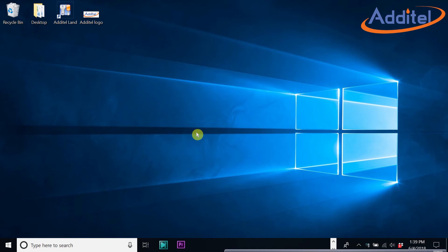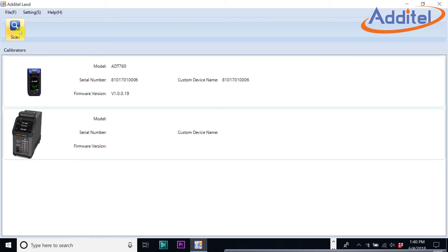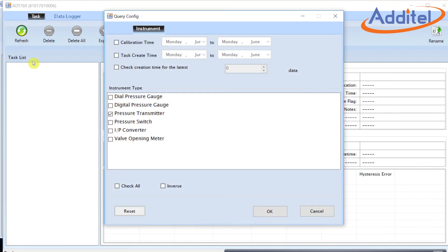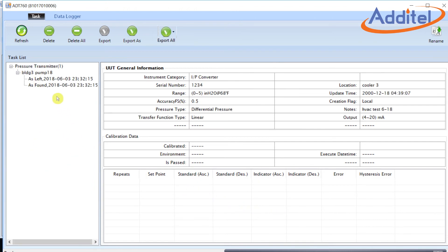Simply attach the ADT760 to your computer via USB or through the wireless option, and then click on the Additel Land app. Once Land is launched, simply click the scan button. The Land software will go out and look for any instruments that it can find. In this case, we can see our ADT760 at the top of the list. After selecting the 760, we'll click on the refresh button. From the query dialog box, we'll want to make sure that the pressure transmitter option is selected, and then click OK. From here, we should be presented with a list on the left. You'll note our as-found and as-left data.